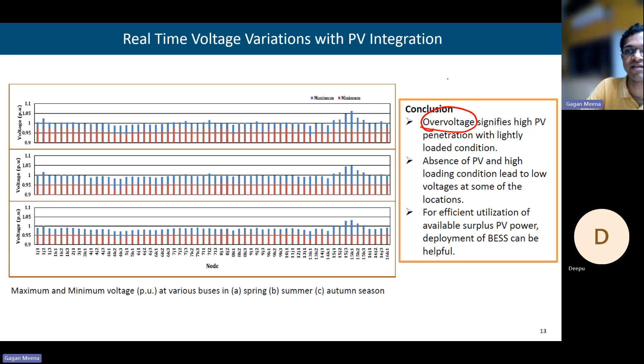This is the real-time voltage variation in PV integration. Here, as we already discussed, over voltage occurs when there is excess generation compared to the load, which signifies high PV penetration with a lightly loaded condition. The generation is more than the load, and because of that there is over voltage. Then we also see under voltage when there is absence of PV and high loading condition, which leads to low voltage at some locations. That's why, for effective utilization of surplus PV, deployment of energy storage can be very helpful.